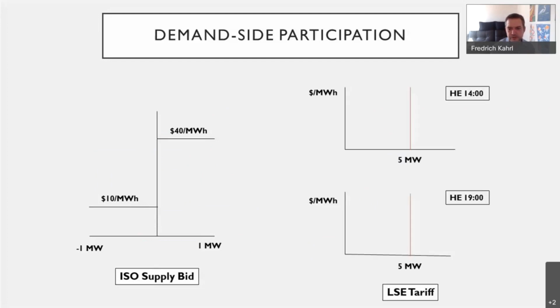And if it's higher than $40 a megawatt hour, it will discharge. On the demand side, there are two ways to replicate what would happen with the supply side offer curve. The first would be through a load serving entity, or LSE, tariff that reflects expected ISO day ahead market prices. So the battery would charge during expected lower price hours and discharge during expected higher price hours. This would show up in the LSE forecast rather than explicitly in its demand bid.